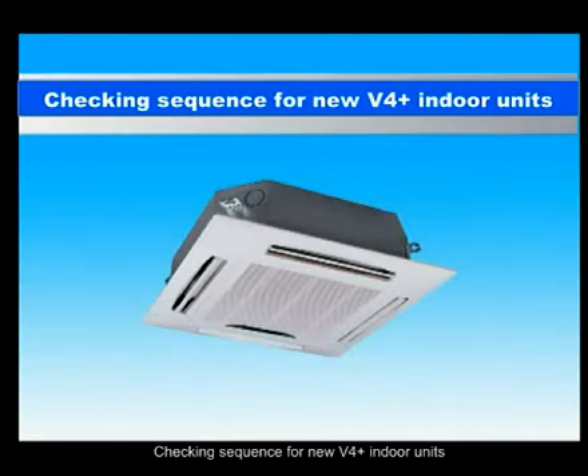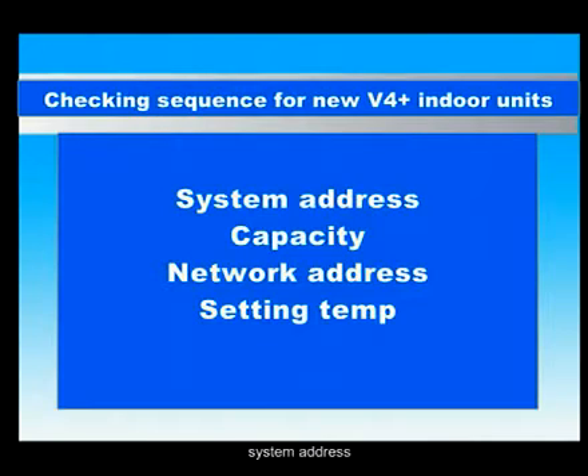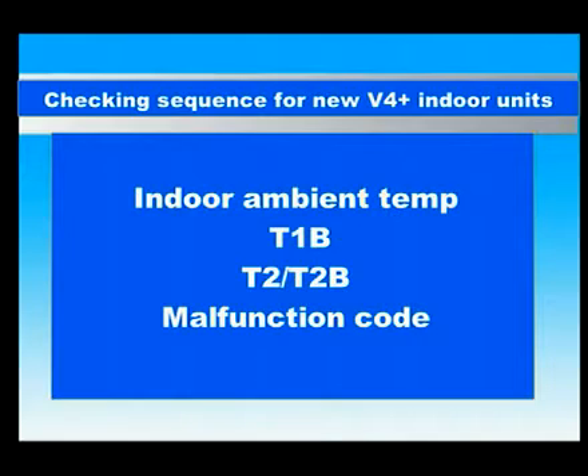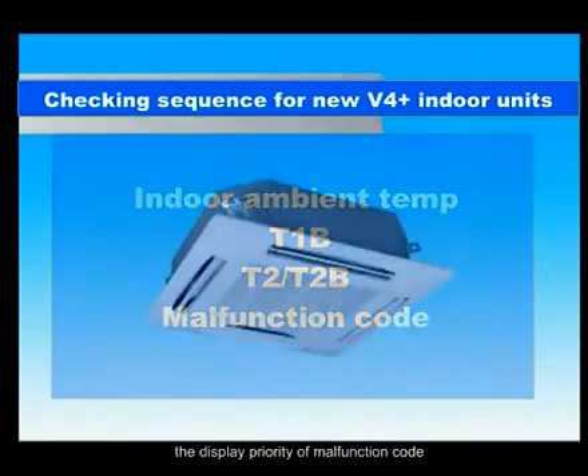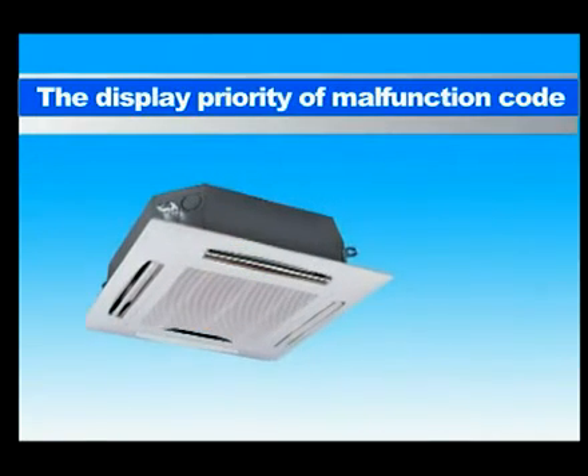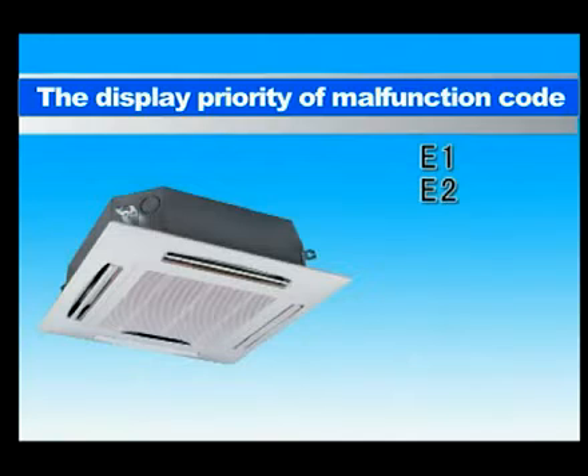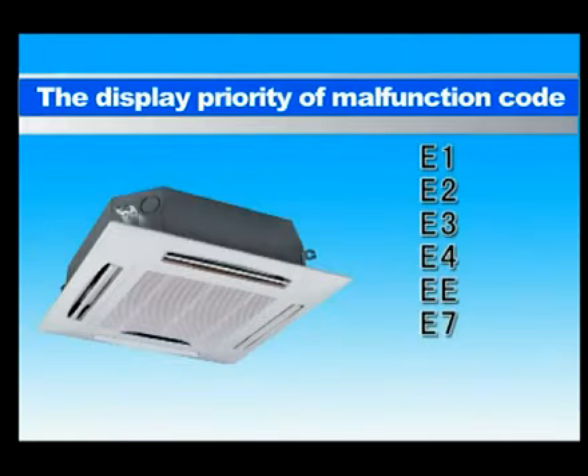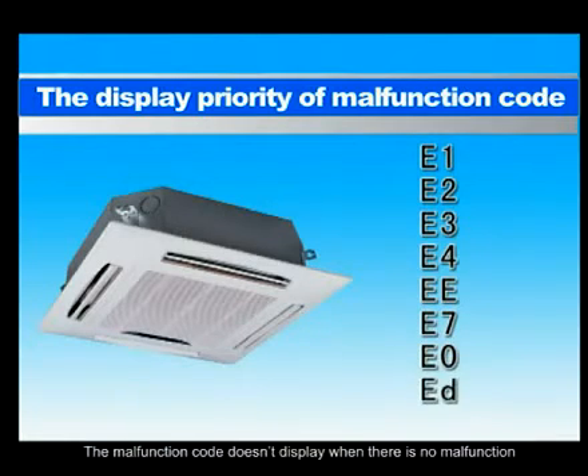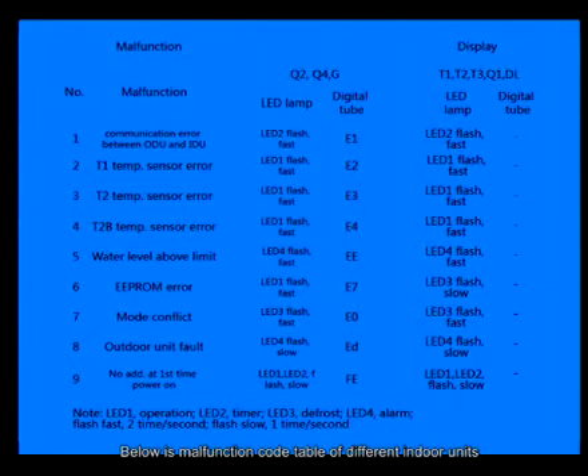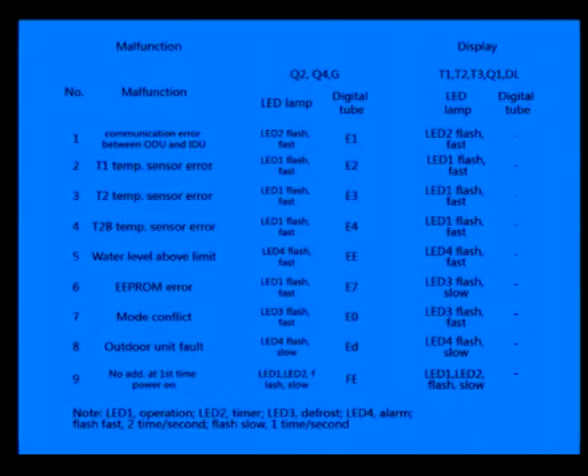Checking sequence for new V4 Plus indoor units: system address, capacity, network address, setting temperature, indoor ambient temperature, T1B-T2/T2B-malfunction code. The display priority of malfunction codes is E1, E2, E3, E4, EE, E7, E0, ED. The malfunction code doesn't display when there is no malfunction. Below is the malfunction code table of different indoor units.